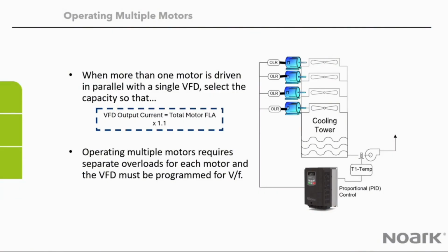You may encounter applications where you need to control multiple motors from a single drive. In this application here, we're looking at a drive controlling 4 motors for a cooling fan. Those motors will ramp up and down, speed up and down based on the one drive. In these applications, you would want to size them by adding the full load current of each motor together, plus about a 10% tolerance.